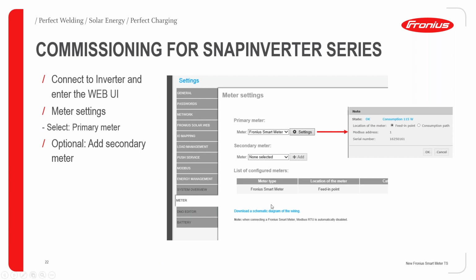data manager. In this, there will be a menu called meter. You have to choose what meter. If it is a Fronius Smart Meter, or it will show S0 meter. So just choose Fronius Smart Meter, and then you have to choose if you have installed the smart meter in the feed-in point or the consumption point. Then click OK. You can also cross-check the Modbus address here if you are choosing the right meters. Then if you have any secondary meter, you can choose it, and then you can add where you have placed it, or you can name it differently. That's optional.